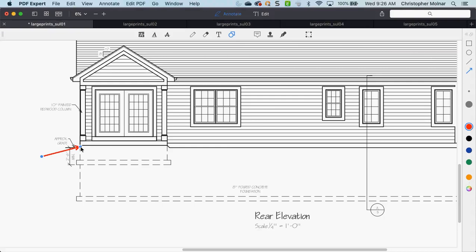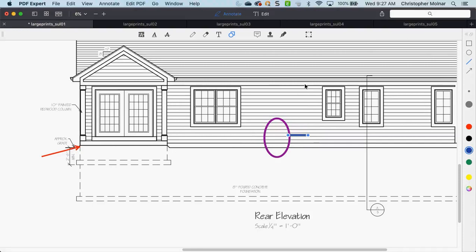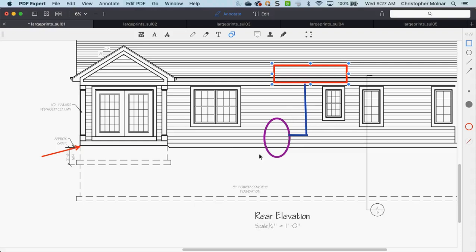Approximate grade is important. When I'm setting a condenser, I need to know where the grade is — the line of dirt, the top of the landscaping — so I can plan the length of my line set running out of the condenser and up through the wall to the attic air handler. I need to know different lengths to plan material, insulation, and placement, because I have to put a concrete pad under the condenser. Legally, I can't just put it on dirt. And if there's a downspout right there, I'm not going to put the condenser there.